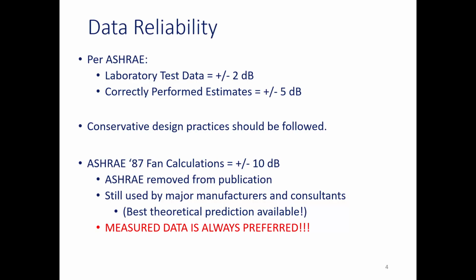If you go all the way back to 87, they published these fan calculations for predicting the noise from fans. They found that the accuracy of that was plus or minus 10 decibels. I think because of that, they removed it from their publication. It hasn't been published since, but it's still the best prediction tool if you're starting from scratch.